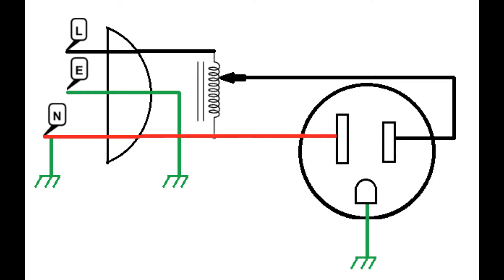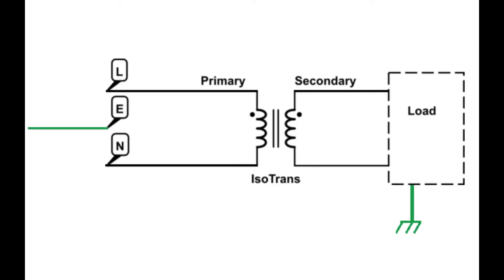Now let's have a quick look at the schematic for an isolation transformer with a load. As you can see, my earth leads into the isolation transformer, and I also have an earth on the chassis of my load. Now with this setup, there's no direct connection between my load's earth ground and the earth ground of my house's electrical system.